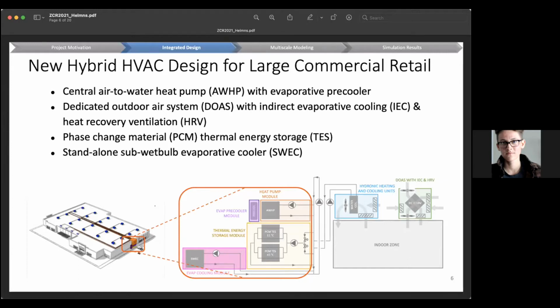Air-to-water heat pumps can do both heating and cooling of this water. In our technology solution for large commercial retail stores, we accomplish that with this set of components: our air-to-water heat pump, our phase change thermal storage at a cold temperature of 11 Celsius and a warm temperature of 43 Celsius, and one additional component, the sub-wet bulb evaporative cooler, which under appropriate climate conditions can provide cold water to serve building air conditioning needs or charge up our cold thermal storage.